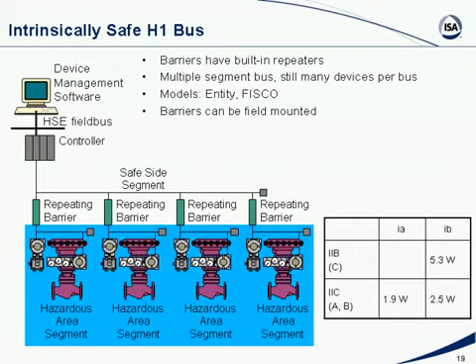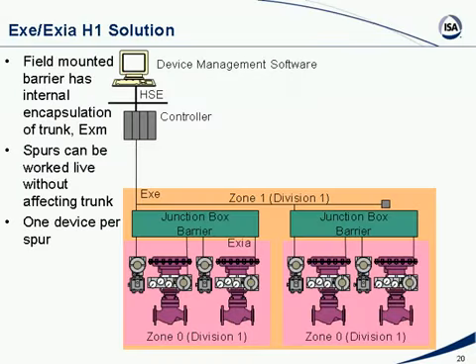Next, we'll take a look at the high power trunk concept, okay? So really what you're doing is you'd have a non-intrinsically safe trunk, okay, and that way you can put many more devices on the bus, simply by moving the barrier into the field, okay. Let's take a look at what that looks like, okay.